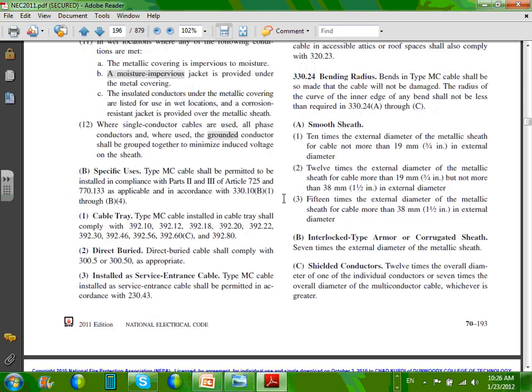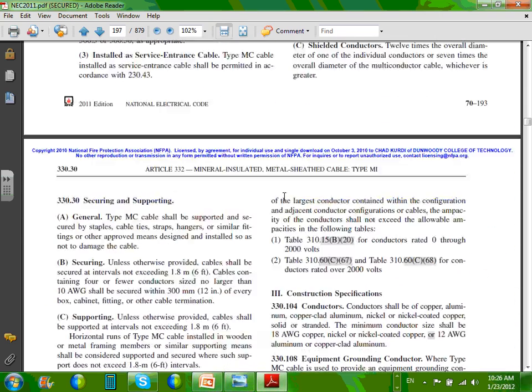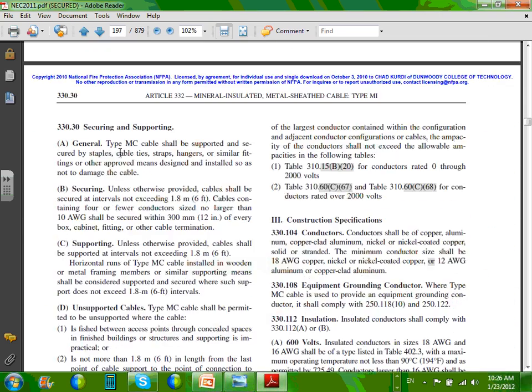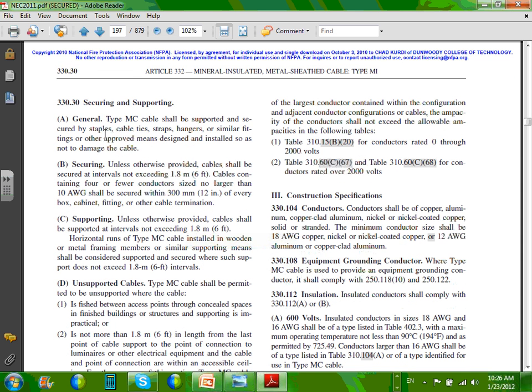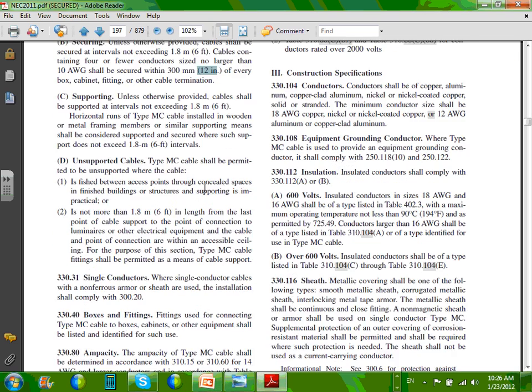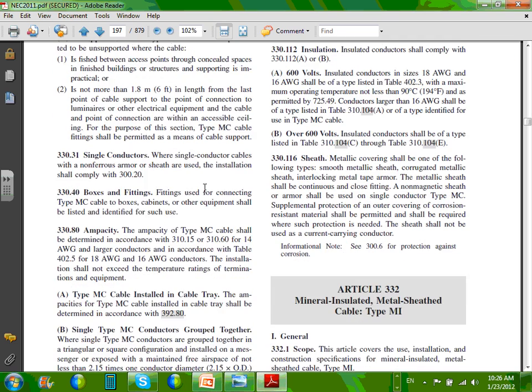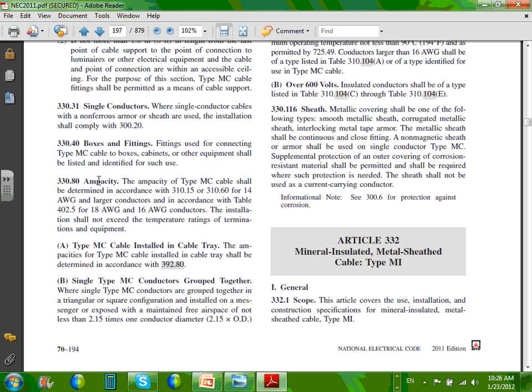And it talks about the bends, how many bends you can use through it, and so forth, shield, and so forth. Support, how do you support it, guys? We talked about the supporting, securing, and support 6 inches, provided shall be secured at intervals of 6 feet, as well as 12 inches from a box. And more details about this ampacity. Here's what we got, the ampacity, guys.